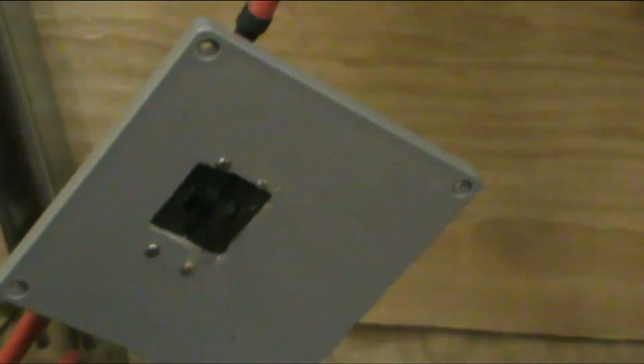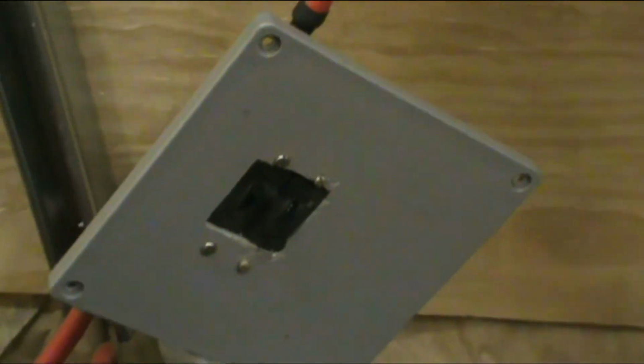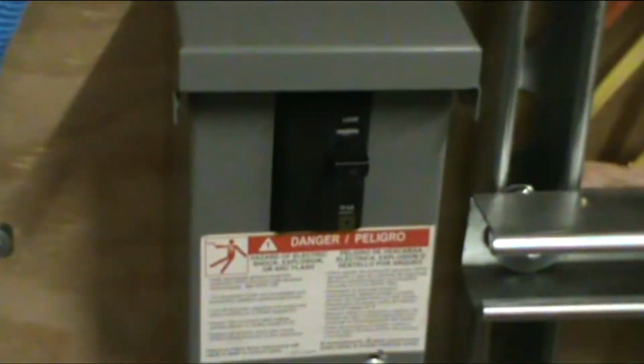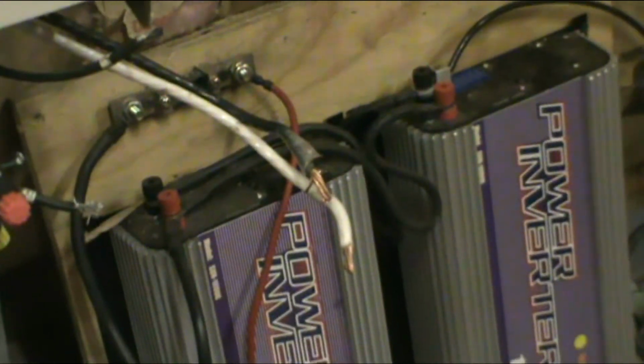I'm still waiting on breakers. Right now I just got that temporary breaker, just 50 amps on there, because I'm not powering any loads off of it. I've got this breaker off for this, because that can be putting out 240 volts out. I have already tested it, and those two leads would have been live, but right now those are off. But there is 240 volts going to this plug here, so obviously everything is hooked up correctly with neutral. So everything is hooked up, boys. We got power coming in from the grid, charging the batteries.